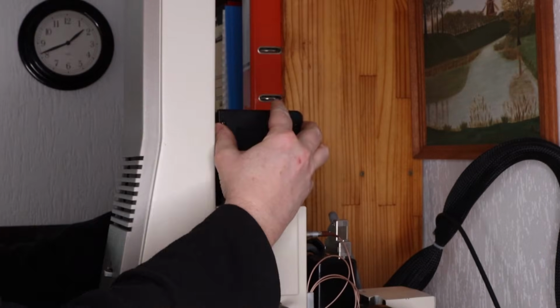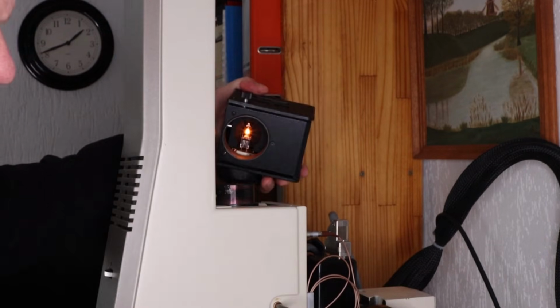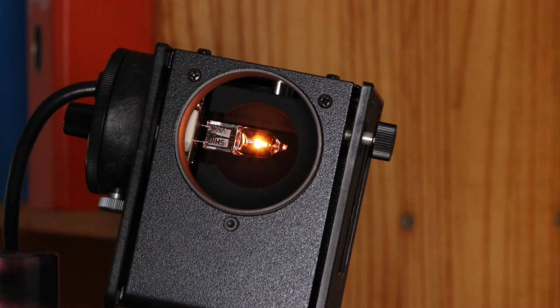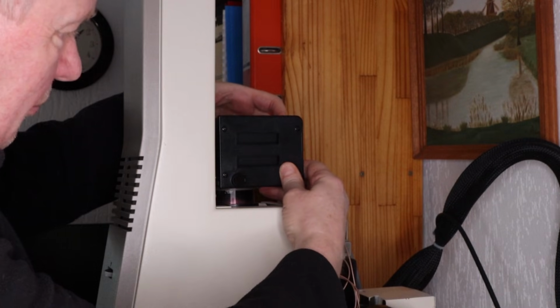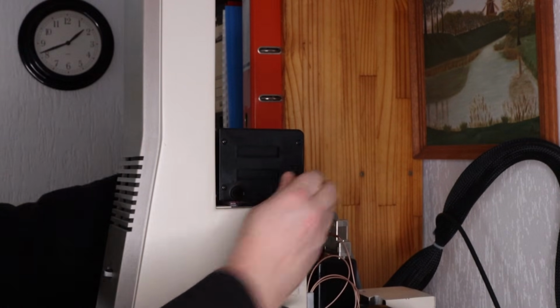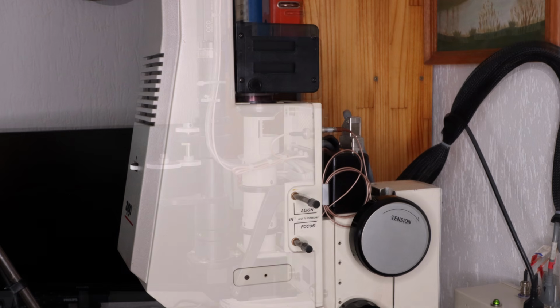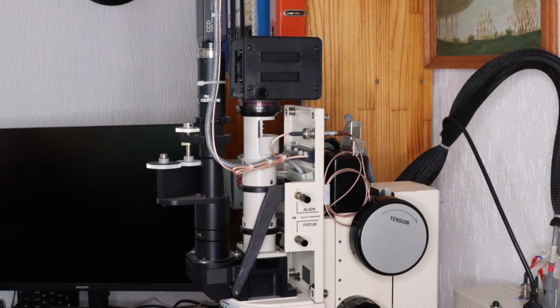The light source itself is an ordinary incandescent lamp, which looks as if it contains quite a bit of infrared, which is actually an advantage because the broader the spectrum, the narrower the coherence pattern. Let's remove the cover and take a quick peek inside at the configuration. The light from the lamp is made spatially coherent using the optical assembly contained in this tube here.